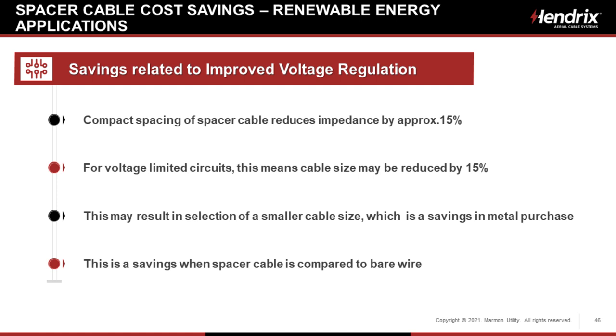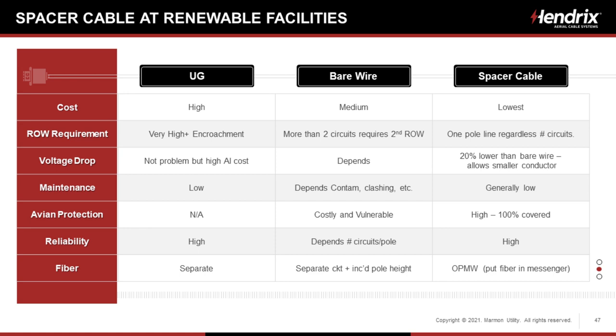How about improved voltage regulation? Compact spacing of spacer cable reduces the impedance by approximately 15%. And this has been covered in previous webinars. If anybody has a question on that, you can send that to me directly. I'd be happy to cover any of these engineering issues in intricate detail with you personally or as a group. For voltage limited circuits, that means the cable size may be reduced by 15%. So this is going to allow us to select a smaller cable size, which is a massive savings in metal, aluminum purchases. So that's a savings when we're comparing spacer cable to bare wire. If you're comparing it to underground cable, it's a slam dunk.